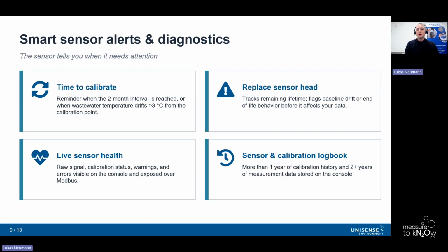Then in terms of smart sensor alerts and diagnostics, as said before, the sensor is self-aware and monitors itself. So you no longer have to remember when to calibrate or when to change the head. There are 4 primary things that it keeps track of. So first, the time to calibrate. It will automatically alert you every 2 months or earlier, depending on the process temperature drift, if that has moved more than 3 degrees from the calibration point.